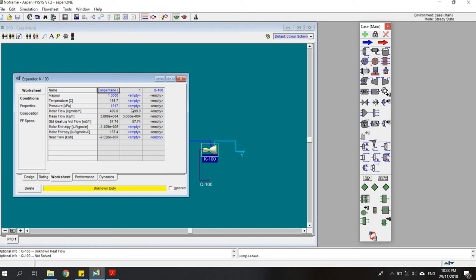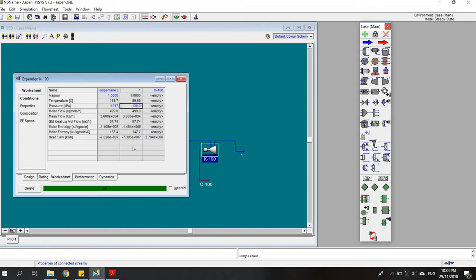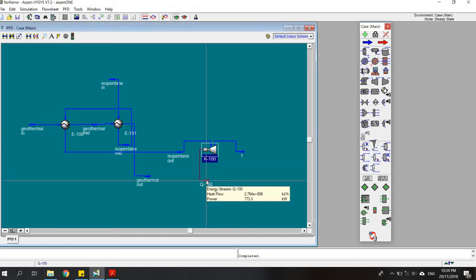We define the condenser pressure leaving the turbine. In this case, I would set it to be a bit above the atmospheric pressure, which is 130 kPa. It will calculate the vapor phase, which is still 100% vapor, which is really good.